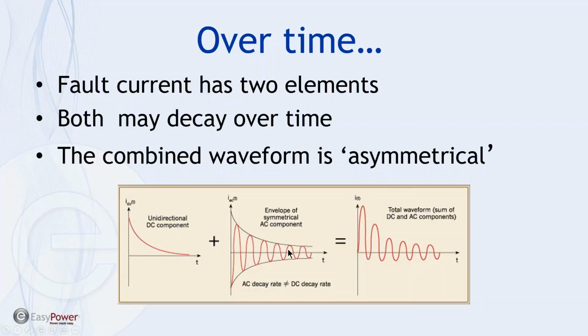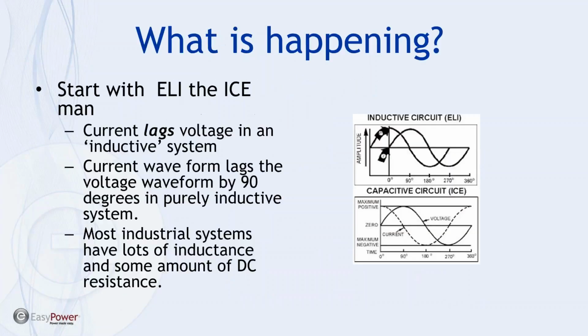The waveform is balanced. Now, at the same time, depending upon the fault origination and some of the other factors in the system itself, there will be a DC offset introduced at the time of the fault, at the location of the fault, and this causes a DC component, again, usually short-lived, anywhere from 10 to 30 cycles of a decaying DC component. And as that's applied in the fault itself, we get what's referred to as an asymmetric waveform, and that's because it's the total sum of the DC and the AC components. So the question is, what's happening and where is this coming from?